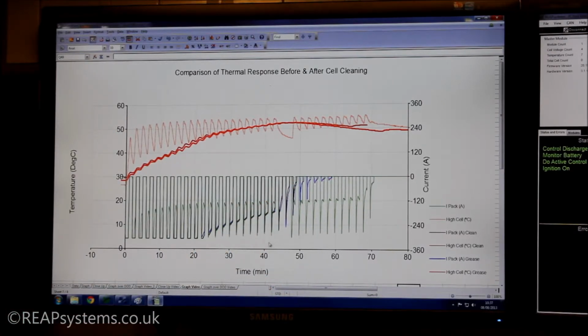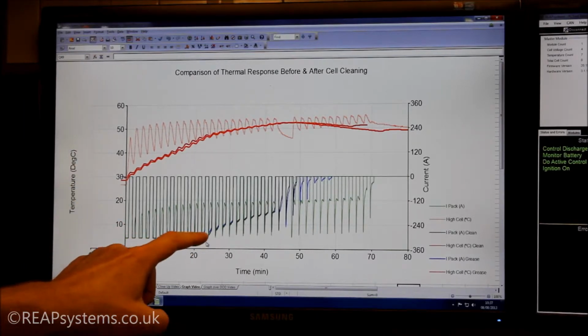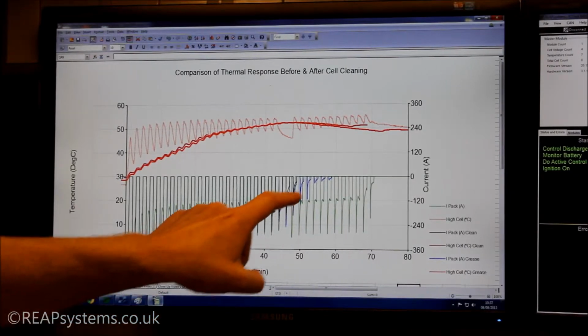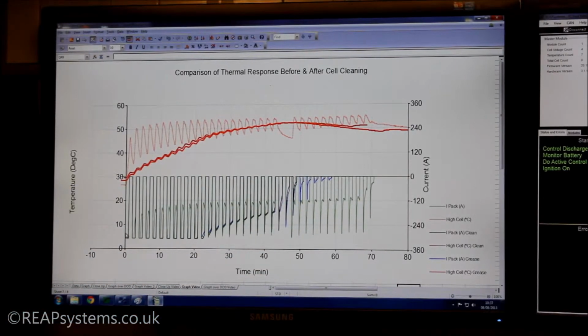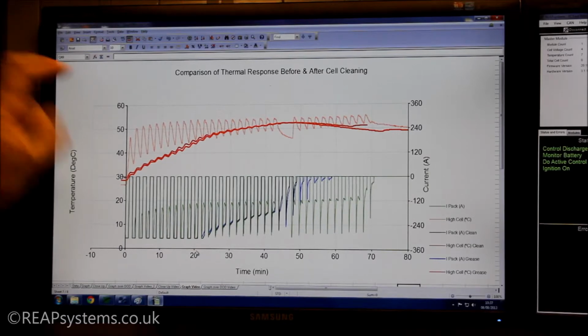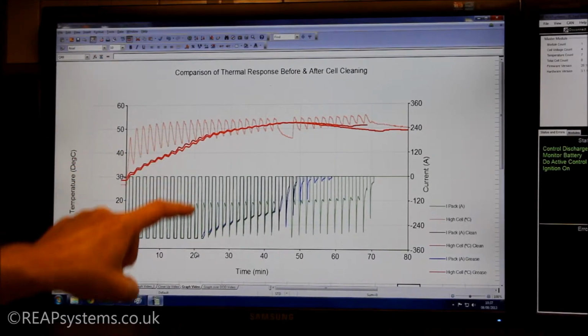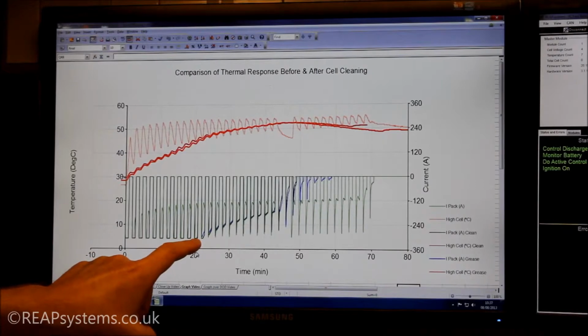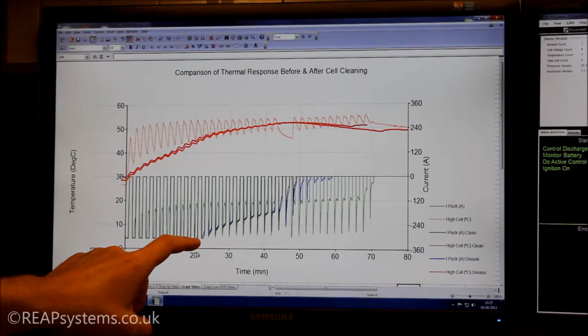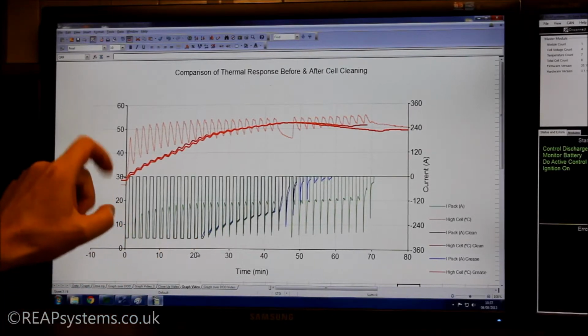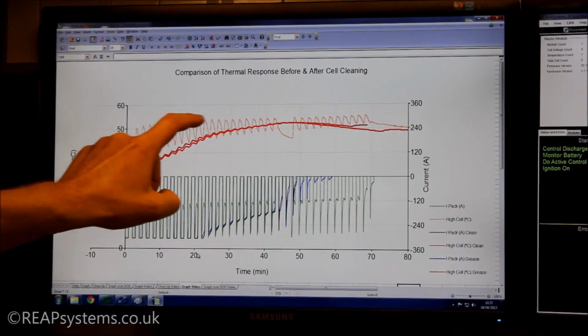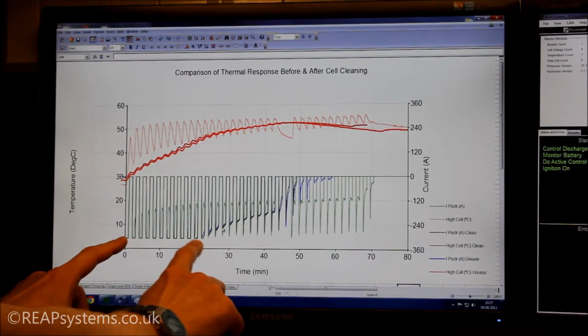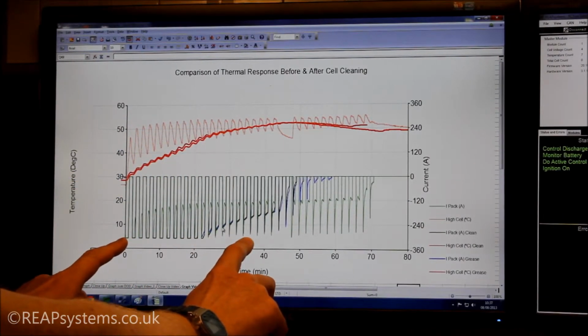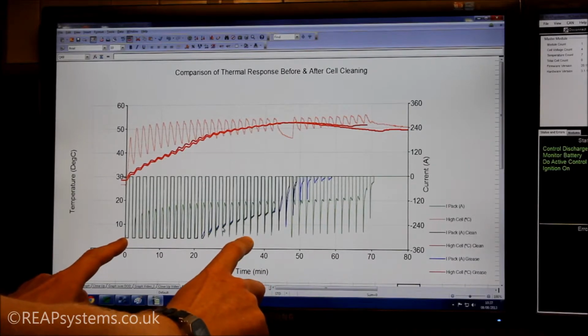The results for the greased terminals are identical. Okay, so no difference between cleaning and greasing. That's right. For this test, we've configured the BMS to start limiting at 45 degrees, which is around here. Yes, and that is to balance performance against life of battery. Manufacturer recommendation is 55 degrees C, so we could increase that temperature to gain longer performance. So if we had increased to 55, we would have elongated the full performance time, potentially, for the whole discharge.